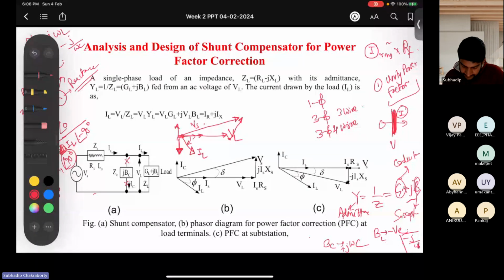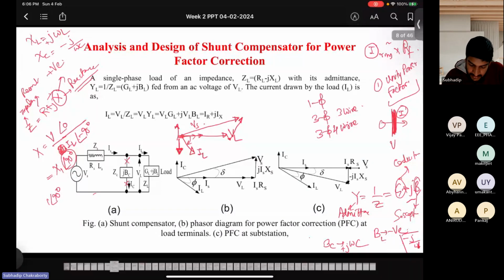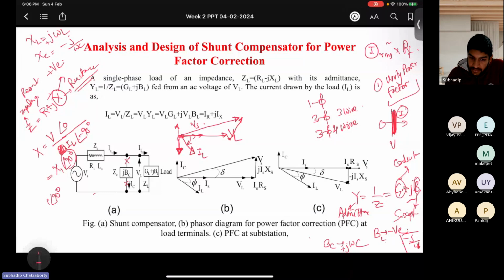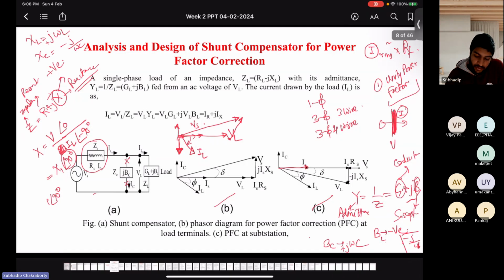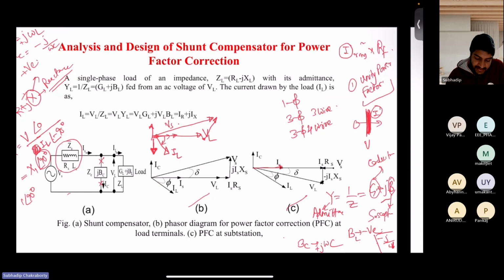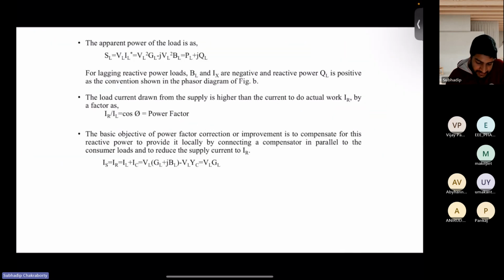So anyone having doubt here? So both types you can do. Either you modify the load power factor, or someone wants to also improve the source power factor, that is at the substation. They will have to push more reactive power using some compensators, and then this current will meet the reactive drop of this impedance. So more reactive power you need, and then you can correct the power factor at the substation, that is, the source voltage, bus voltage, and current are in line.